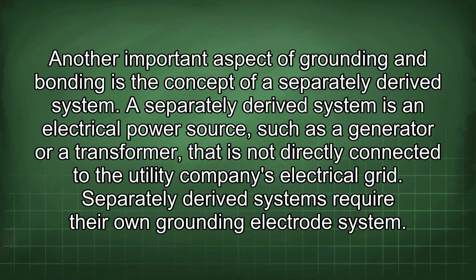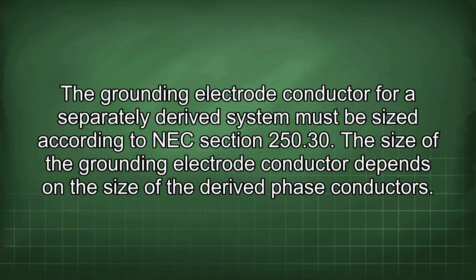Another important aspect of grounding and bonding is the concept of a separately derived system. A separately derived system is an electrical power source, such as a generator or a transformer, that is not directly connected to the utility company's electrical grid. Separately derived systems require their own grounding electrode system. The grounding electrode conductor for a separately derived system must be sized according to NEC Section 250.30. The size of the grounding electrode conductor depends on the size of the derived phase conductors.